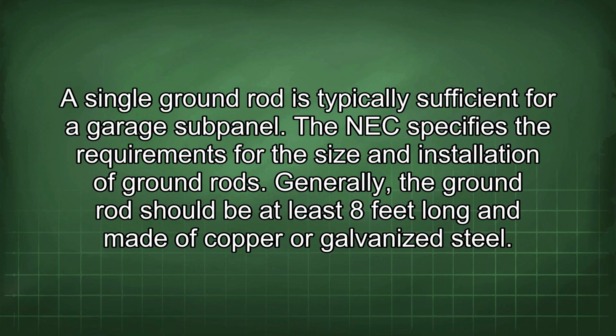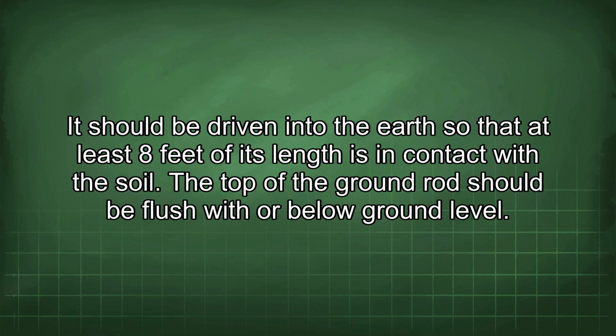The NEC specifies the requirements for the size and installation of ground rods. Generally, the ground rod should be at least 8 feet long and made of copper or galvanized steel. It should be driven into the earth so that at least 8 feet of its length is in contact with the soil. The top of the ground rod should be flush with or below ground level.